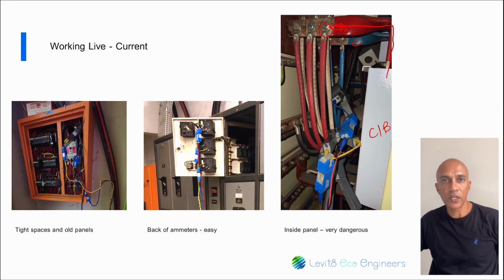Now, if you are using a transducer that uses the existing panel CT secondary wires to obtain current readings, that's not too difficult. You would simply take your transducer, like we showed earlier, and connect it to the incoming or outgoing wire of the panel ammeter. So here we have your panel ammeters in the second photo, and if you notice, the transducer is put around the wire that goes into the ammeter.